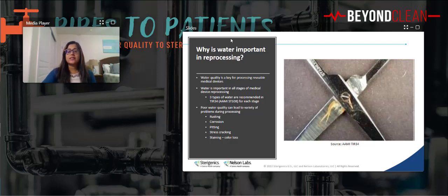Now, water is important in all stages of medical device reprocessing. It's not just important in cleaning. It's also important in disinfection, and it's very important in steam sterilization because that's the last process performed before an instrument is used on the patient. So you want to ensure that as you move along the stages, the water gets cleaner, and it comes to critical water at the end of the process, which I'll go through in detail as well.